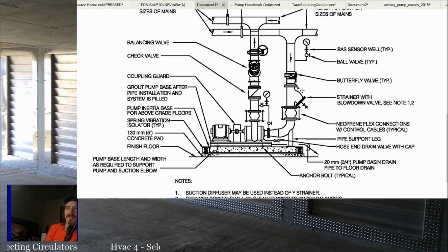Okay? It's not a bad idea to have a strainer, but if you want to err on the side of caution, it's better to have a pump damaged from large debris in the system than to have a strainer and the pump cavitate, because the odds of you getting large debris in a closed loop is usually pretty small compared to the other problems. So with a small inline pump, small circulator, I would not recommend a strainer. On big commercial systems, where the possibility of large debris is a little bit higher, you'll see strainers on the inlet side of the pumps.